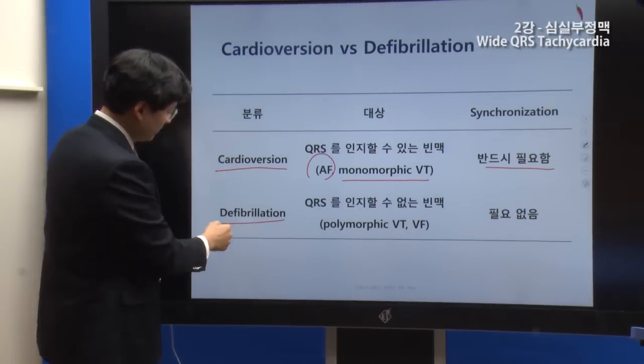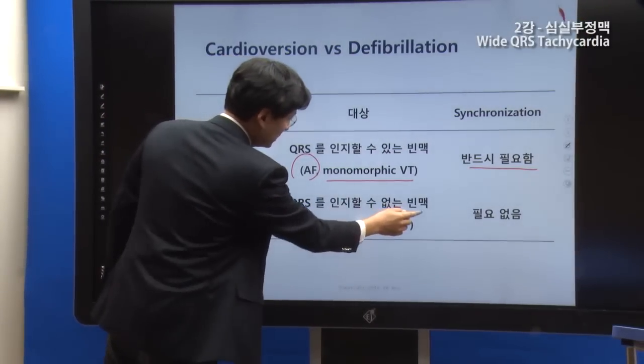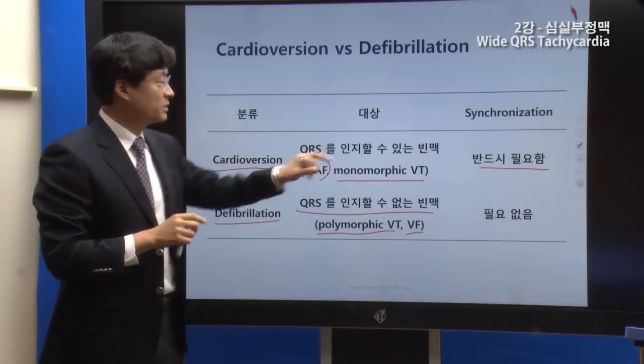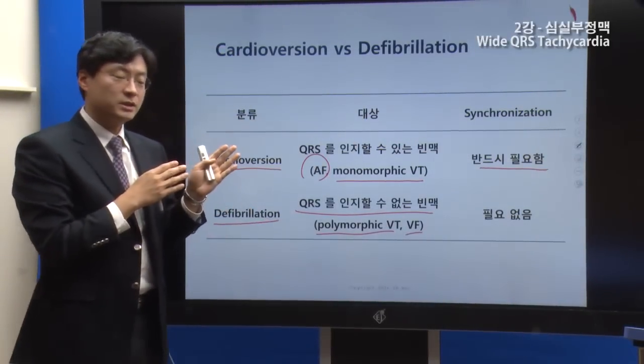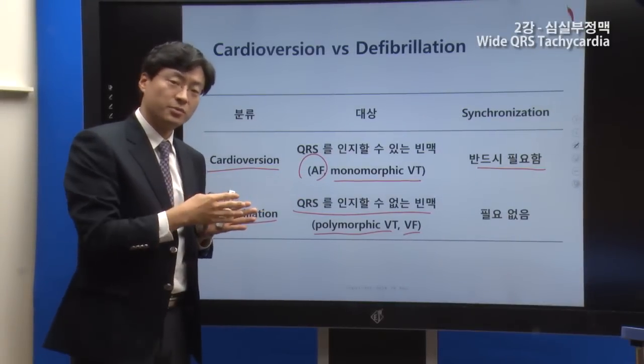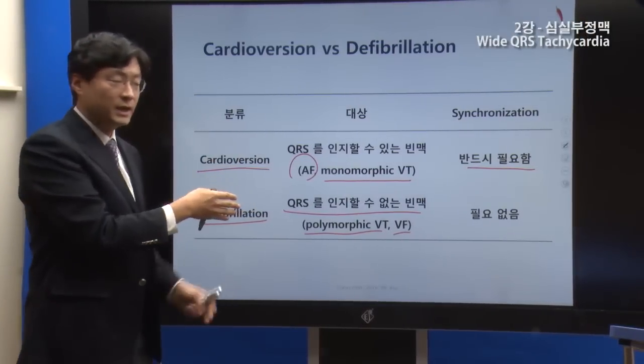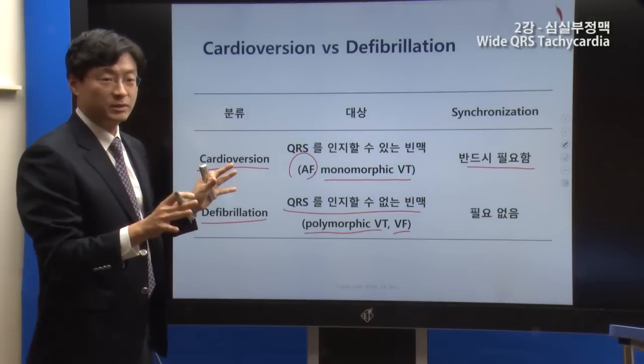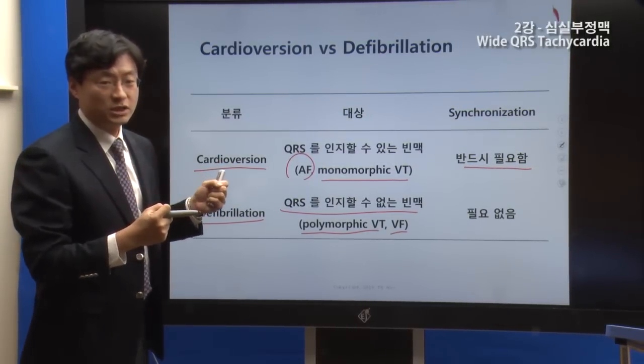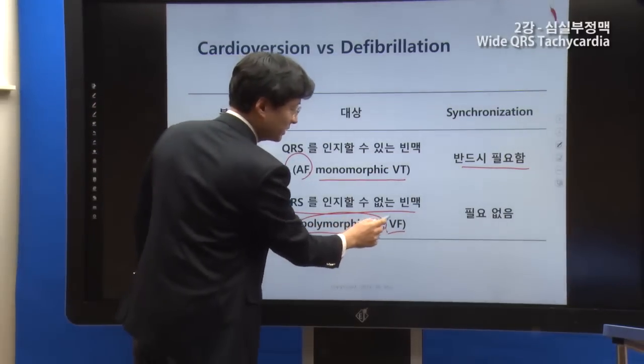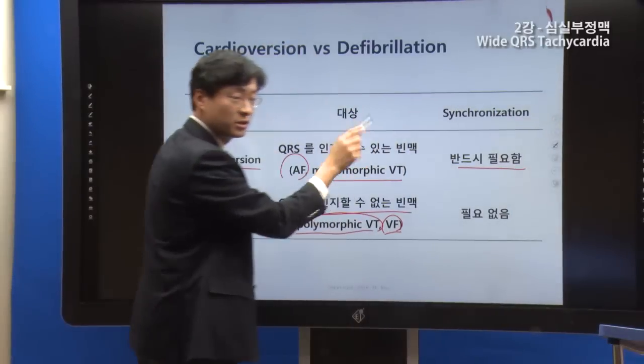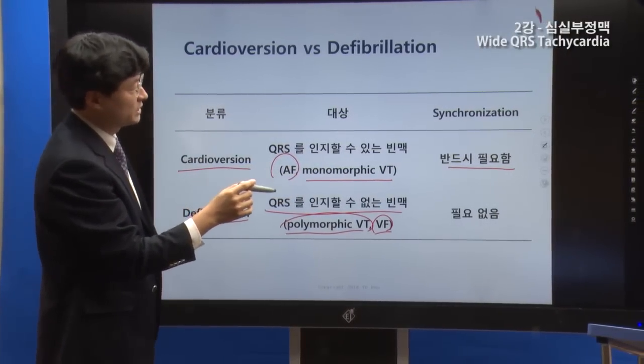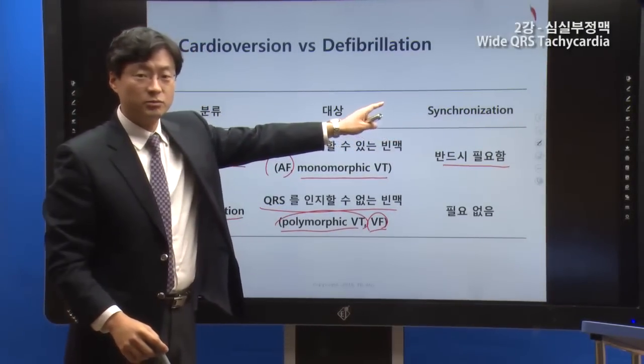For defibrillation, the QRS cannot be recognized. In cases of polymorphic VT or VF, there is no clear QRS. If you use a synchronized device in this case, it cannot read the QRS and therefore cannot deliver the shock. So for polymorphic VT or VF, you must use unsynchronized defibrillation — do not use the synchronized mode when using DC shock in these cases.